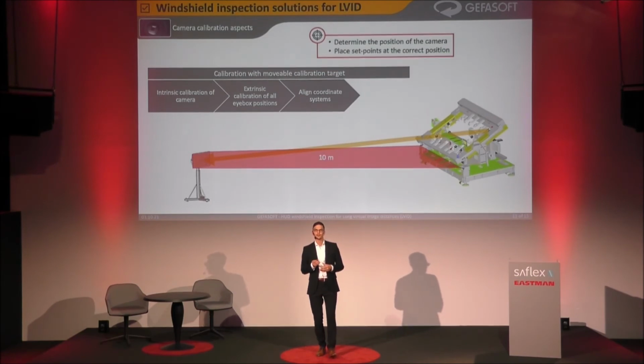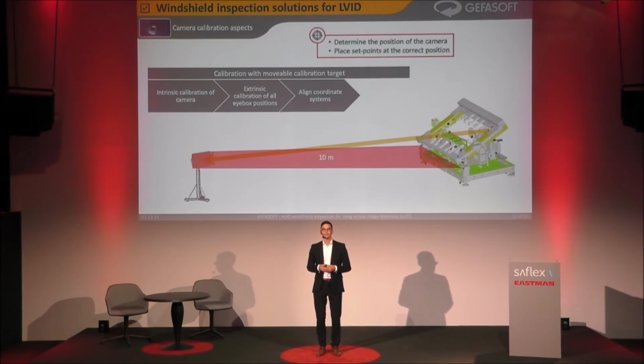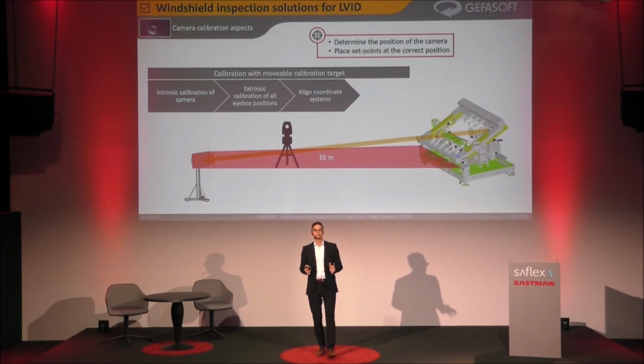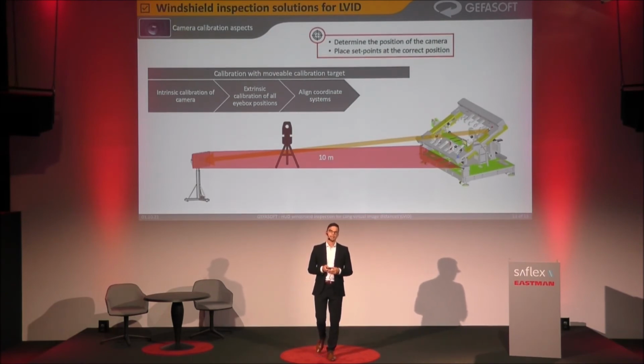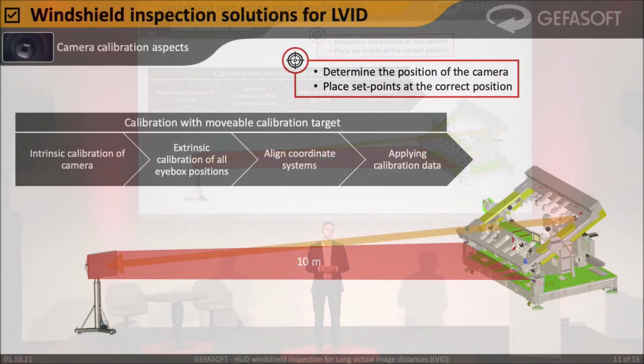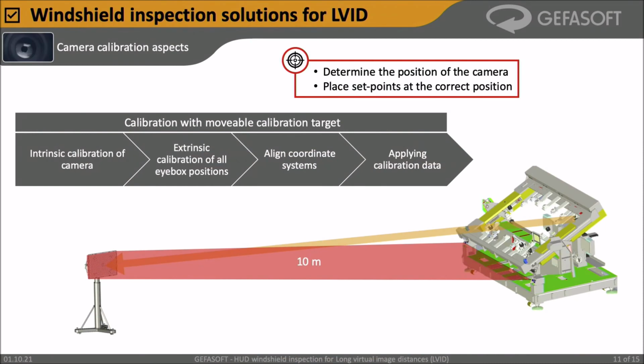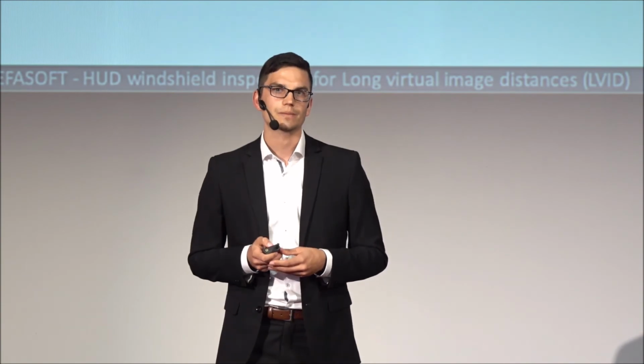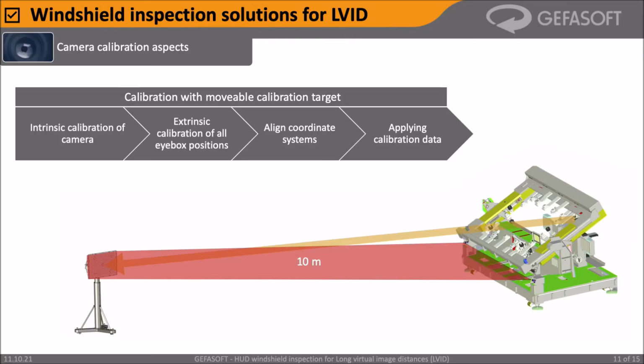Next step is to align the coordinate systems. This is done by an independent measurement system. In this case, we use a stereo camera system, which needs to be initially 3D measured. Then both coordinate systems are aligned together. And in the end, we need to apply these calibration data for our inspection of the windshields. So this is briefly how the calibration procedure works. And of course, this is a system that we can easily adapt in order to inspect longer virtual image distances.